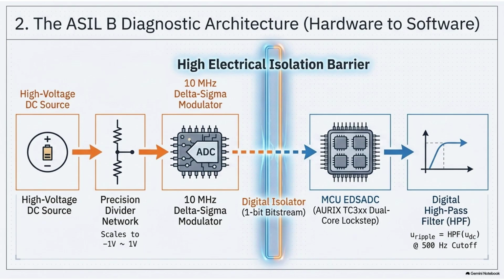It does, but we have to apply the Joule heating principle we mentioned earlier. When you push 200 amps of high-frequency ripple current through even a few extra milliohms of resistance, you generate intense, highly localized heat directly at the connection point. Right. The copper terminals heat up like the coils of a toaster.